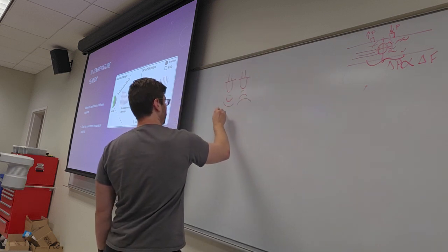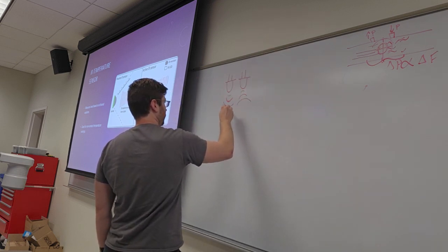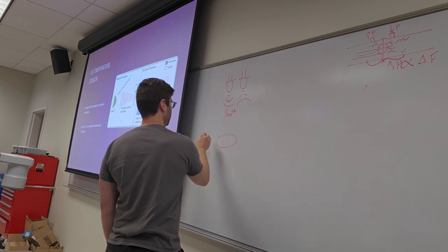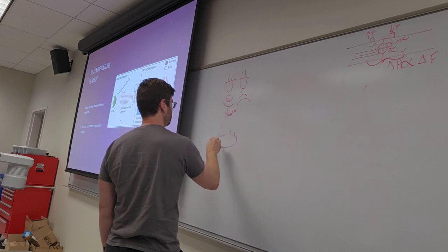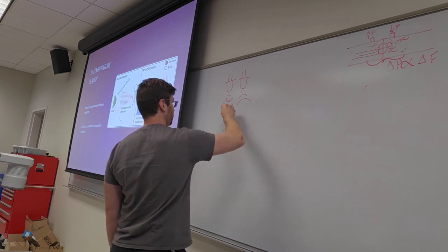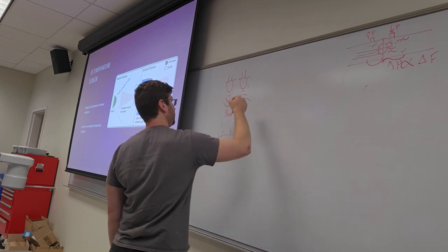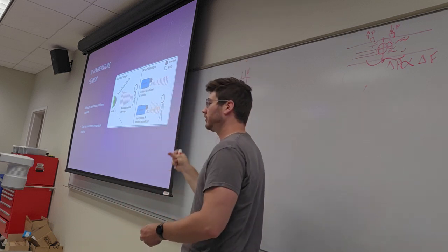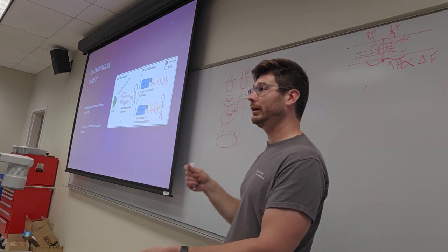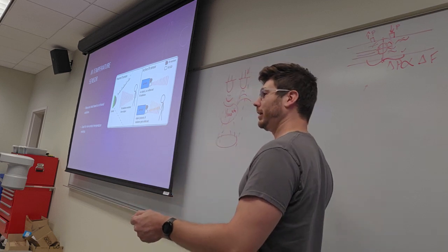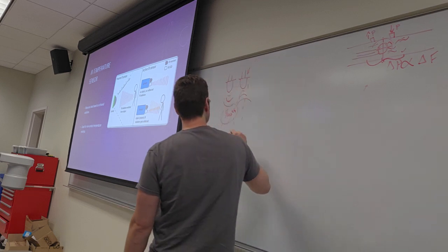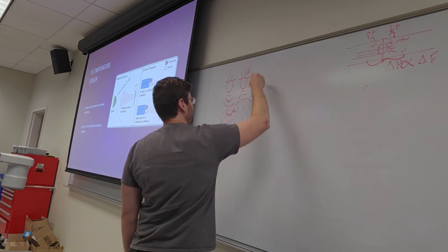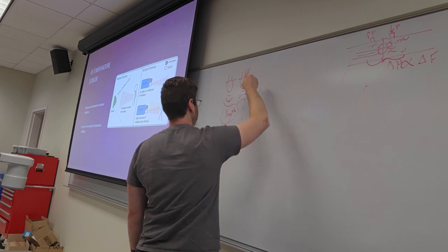So for 1/100th of a second, this light will turn on, it'll blink on, illuminating this light here, right? And that light will be received, again, they will only look during this same 1/100th of a second. It's like a blink. It's like I light up the light and I look for that light and then I don't care otherwise. Okay? It sees how much light was received from that spotlight and then gives a percent accordingly of that maximum.